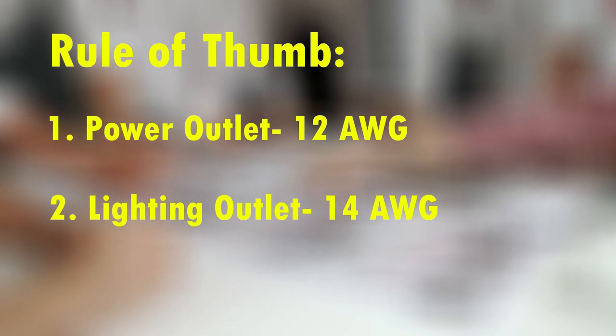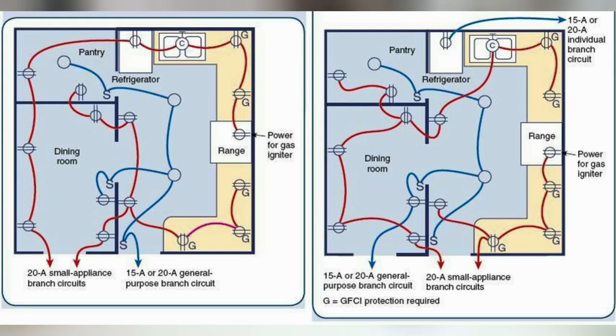Here is a quick rule of thumb: for every single power outlet, 12 American Wire Gauge (AWG) will be selected. For every single lighting outlet, 14 AWG will be selected. But this is not always the case — we cannot assume this will always be safe or economical, especially with multiple outlets or fixtures for branch circuit wire and main circuit cable sizing.